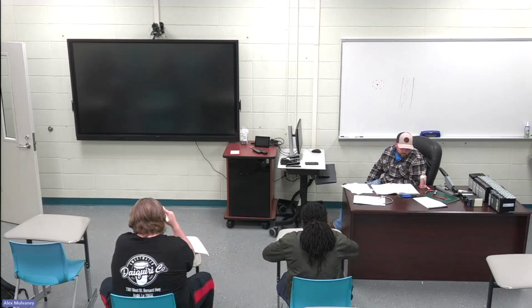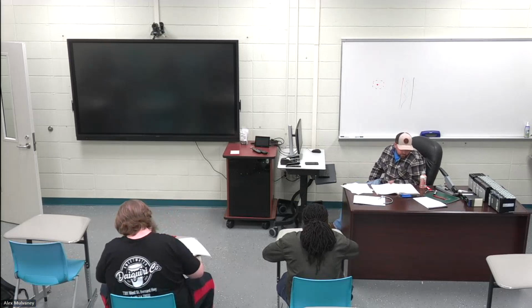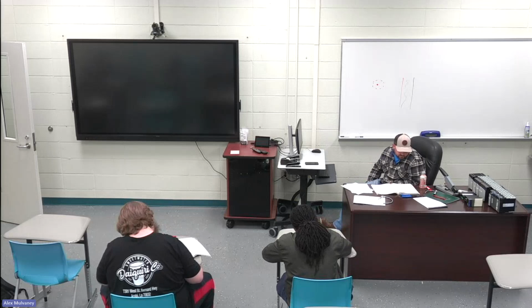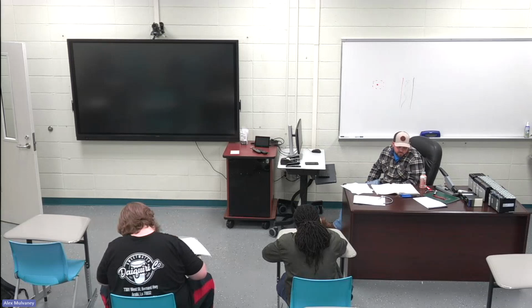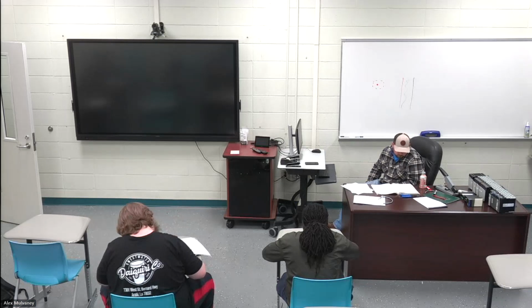Preventing ground loops, 242. First paragraph, last 2 sentences. Improper cable shielding practices can also induce noise problems. If too many grounds are used, a ground loop can result.